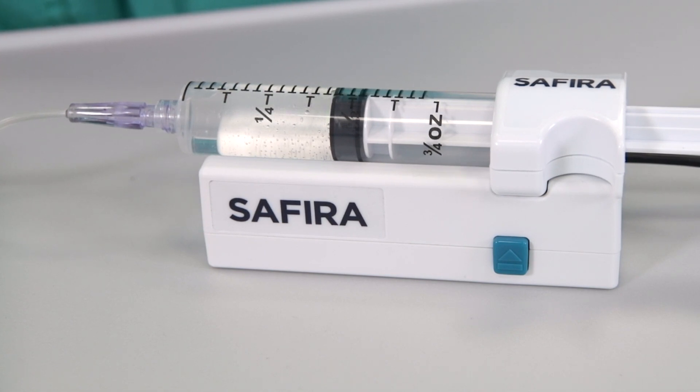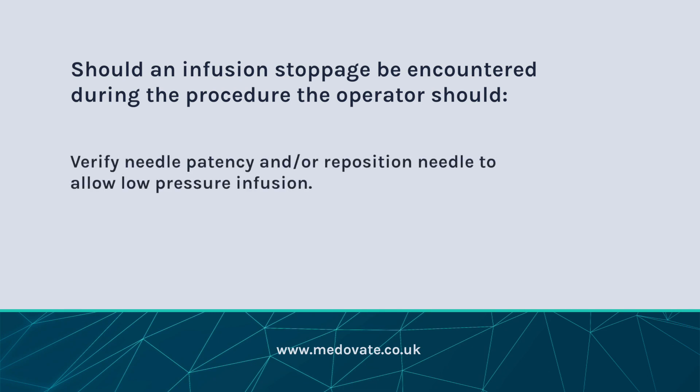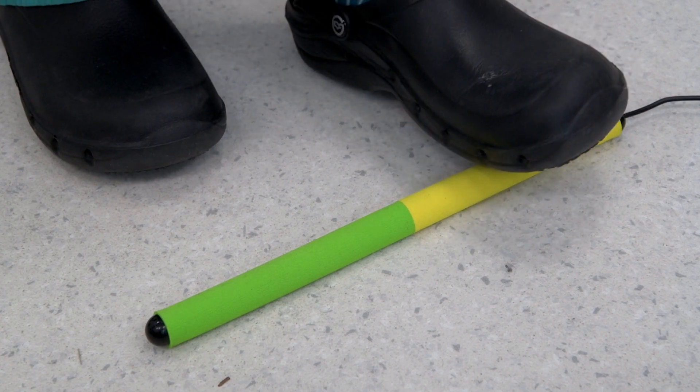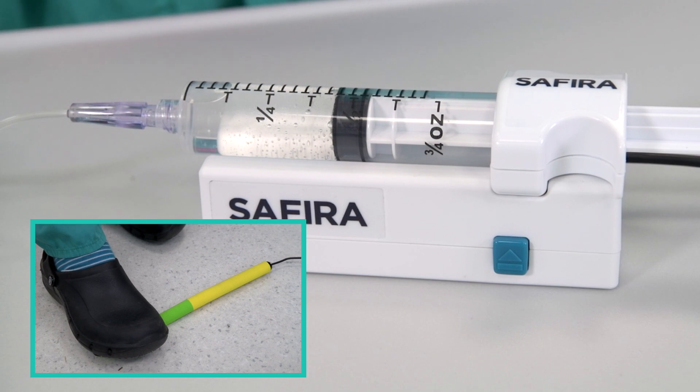If the unit detects an unsafe pressure during the infusion process, the driver will automatically stop infusion and a red flashing light will appear. Should an infusion stoppage be encountered during the procedure, the operator should verify needle patency and/or reposition the needle to allow low pressure infusion, and then reset Safira. To reset the flashing red light on the driver, the operator should aspirate by pressing the foot pedal on the yellow end nearest the cable until the red light goes out. The procedure can then be continued.